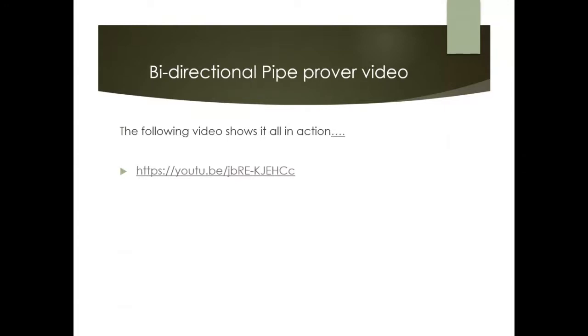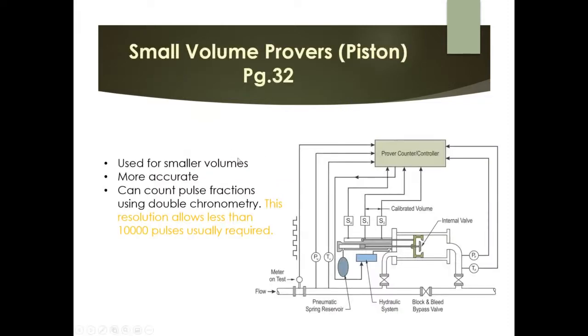That video covered the key points about bi-directional pipe provers effectively. Moving on to the small volume piston prover: these are used for smaller volumes. They are more accurate and have the benefit of counting pulse fractions using double chronometry — a term worth familiarizing yourself with.